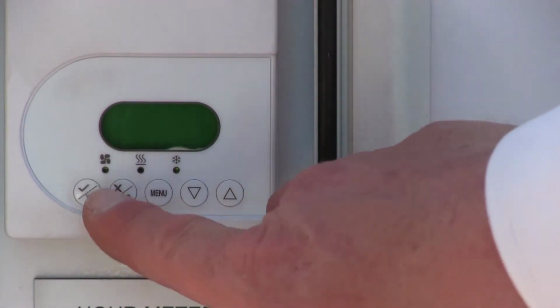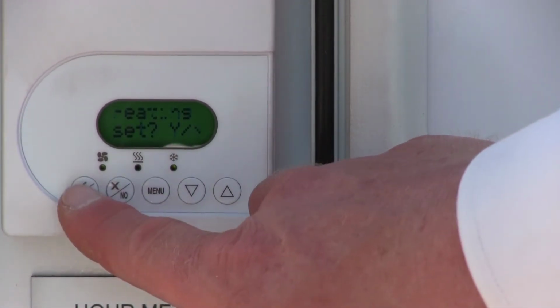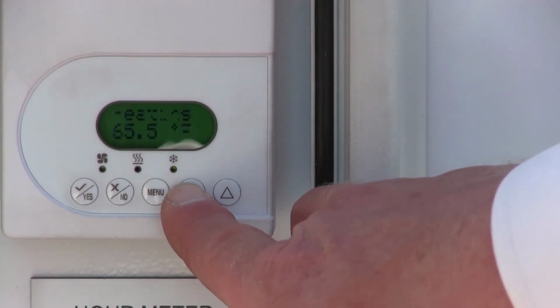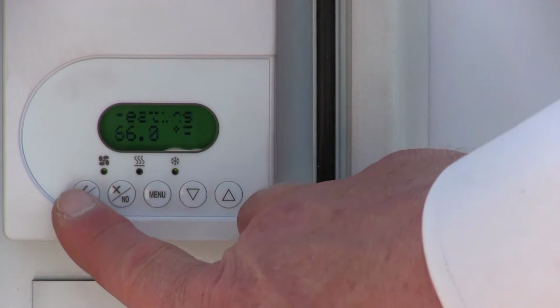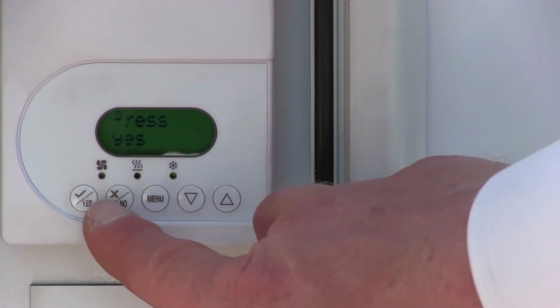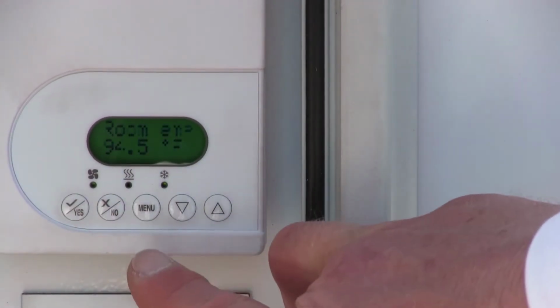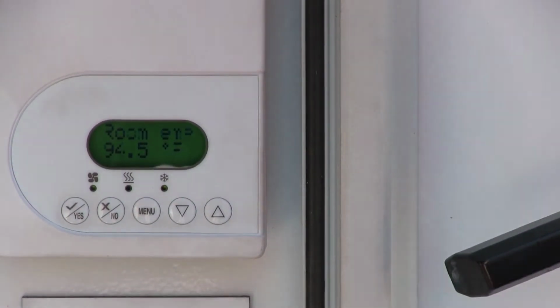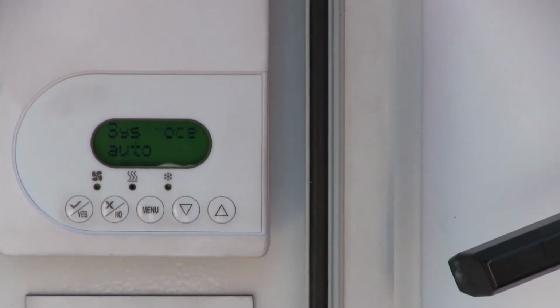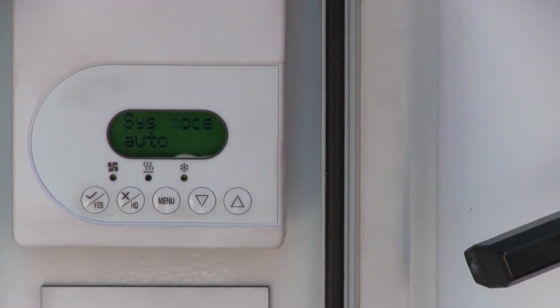Then we'll say yes. And it's going to say, do you want to set the heat? We'll say yes. And we're going to set the heat for 66 degrees. We're going to lower it down right there. And then we'll say yes. And then it's going to say Fahrenheit or Celsius. You say no. It's going to say exit system, yes. And now you're back to your scrolling marquee, but now it's going to show you your room temp's 94.5. The system mode is for auto, and it's currently occupied.